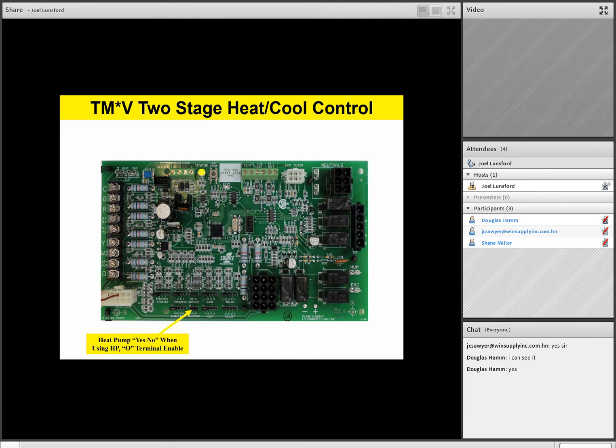The fan speed, where it says fan speed high, medium, low, is for your continuous fan speed. Unlike our previous board that gives you a speed tap, so to speak, this is strictly high, medium, and low. So if the homeowner goes to the thermostat sub-base assembly and goes from auto to on for the fan, how fast will the fan run? That's what this fan speed jumper is all about: high, medium, and low. Now, please write this down. Low is going to be about 35%, and the reason I say about is that it's furnace model specific. But low speed will be approximately 35 to 40% of your cooling airflow. Medium will be 50% of your cooling airflow on your continuous fan speed, and high will be 100% cooling airflow.